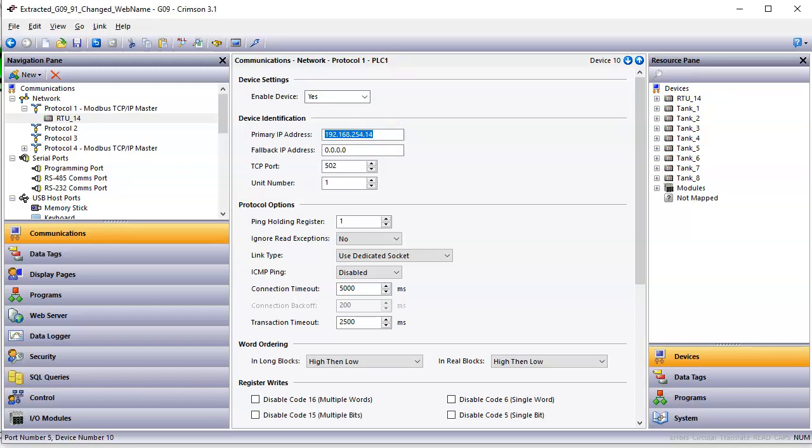And normally, if you were doing this over Modbus, you would use port 502. Now, because I'm cheating and I'm using this same HMI to mimic a PLC, I'm going to share this with 8 to 10 different virtual students, and the Red Lion product will support up to 4 devices on a particular port when it's acting as a slave.